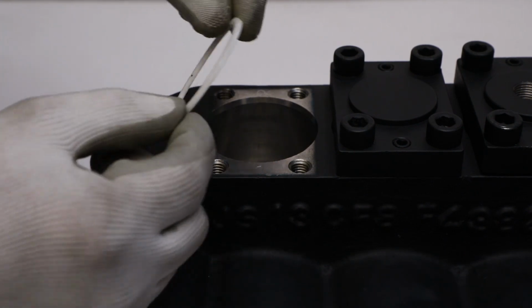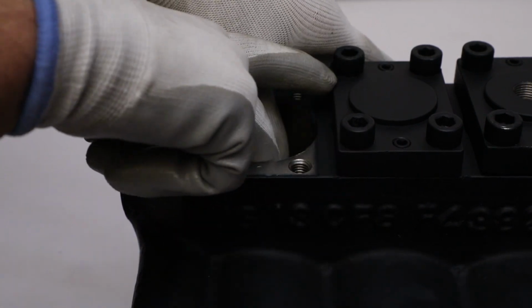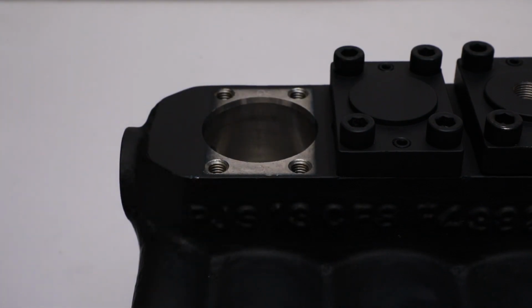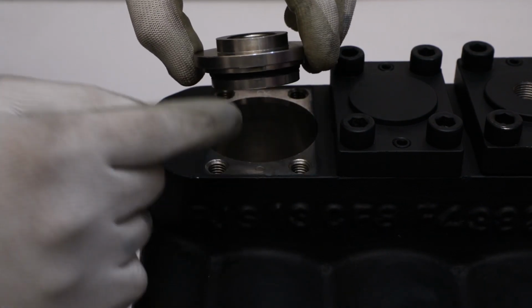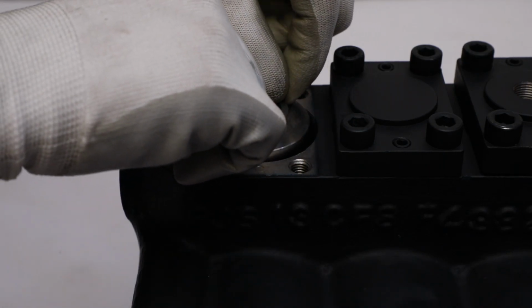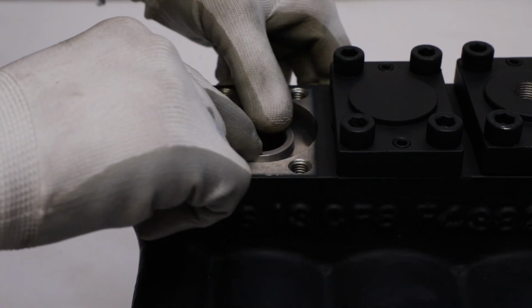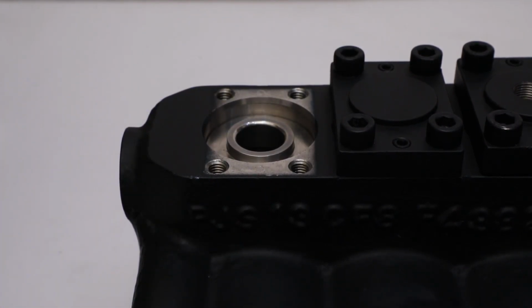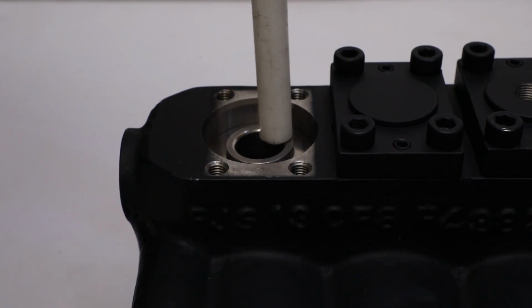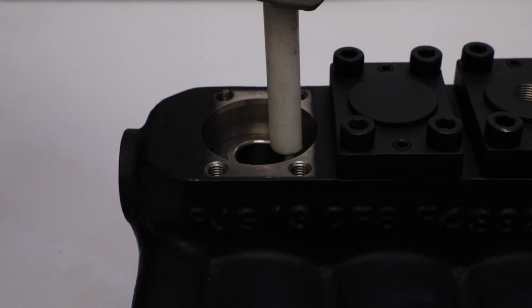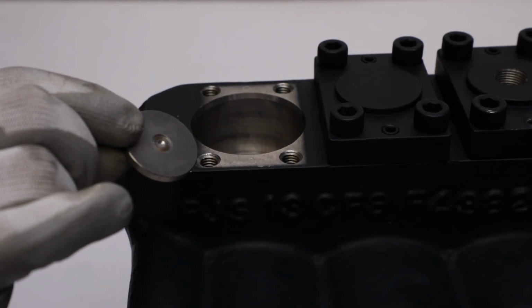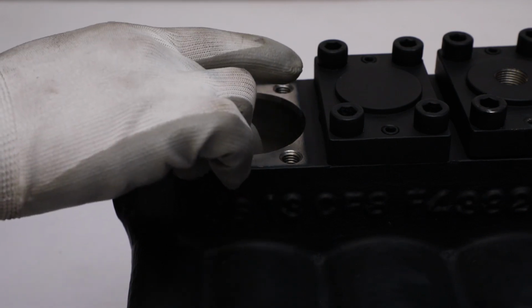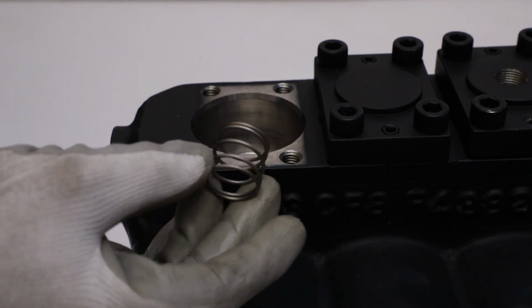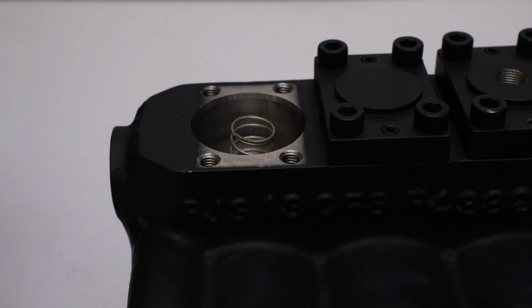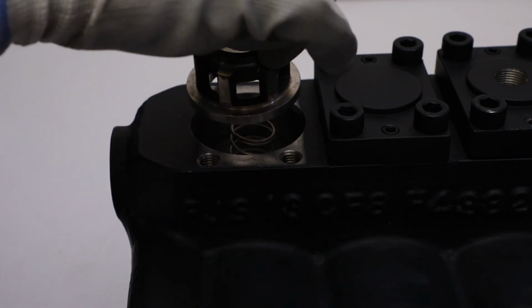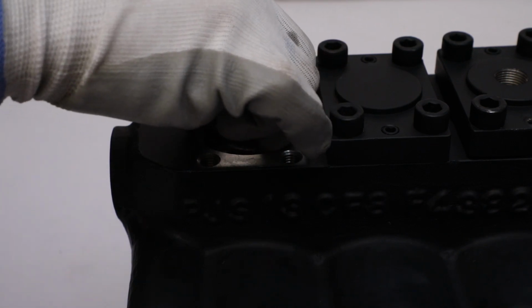After that, put PTFE gasket on suction valve seat guide. Place discharge valve seat having an O-ring side facing downward. Push it in its proper position with the nylon rod and rubber hammer. Put suction and discharge valve plate such that its flat surface will face downwards. Put helical spring on it and then put discharge valve guide facing flat surface with a hole at center upward.